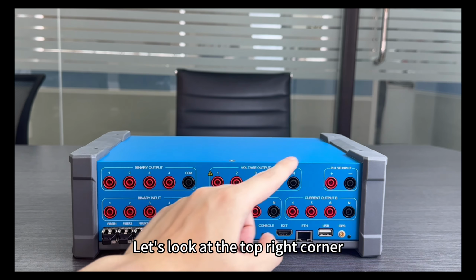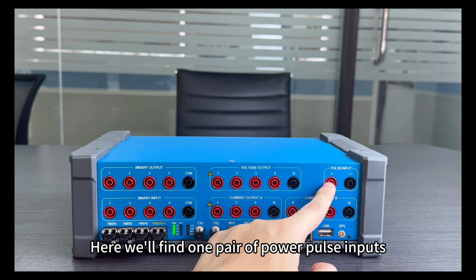Let's look at the top right corner. Here we'll find 1 pair of power pulse inputs, specially designed for precise energy meter calibration. At the bottom, we'll find 4 pairs of LC optical ports that can be configured as either SV transceivers or for GOOSE publish and subscribe functionality.